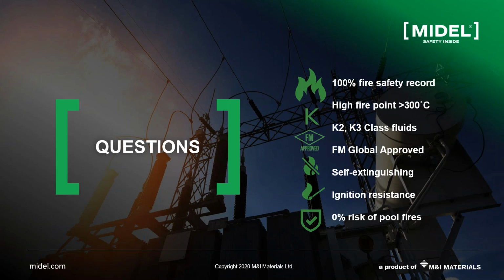So I understand the comment, and this is part of it. Our job at MIDEL is to educate these authorities and agencies, and this is not just in South Africa; it's global. So the movement is going there, but one aspect to recognize is that with a readily biodegradable ester, if you have a spillage, the impact on the environment is really reduced, so cleaning up will be lower. Even if you don't change the substation for bonding reduction, if your statistics indicate you usually have leaks, with an ester you will have lower impact, and so you show responsibility and a reduced impact on the environment, even with no change in regulations.